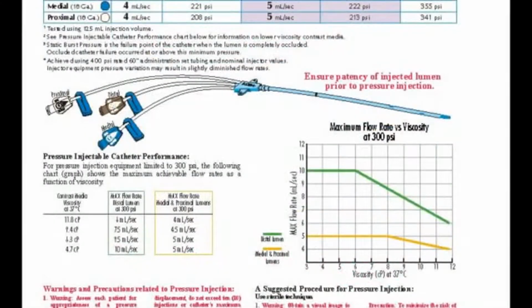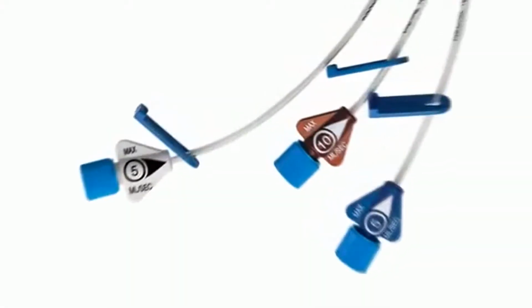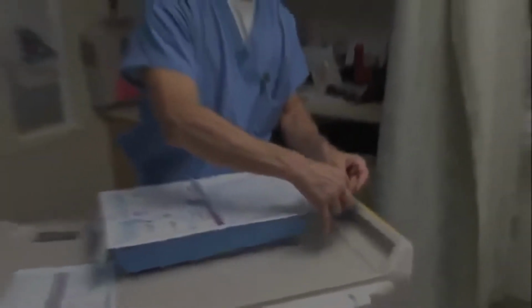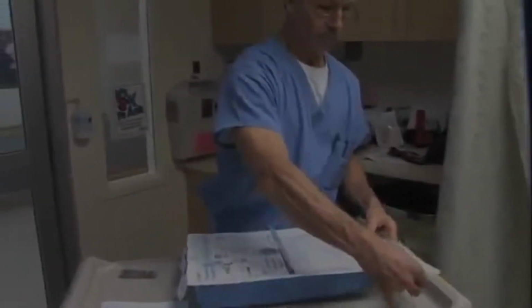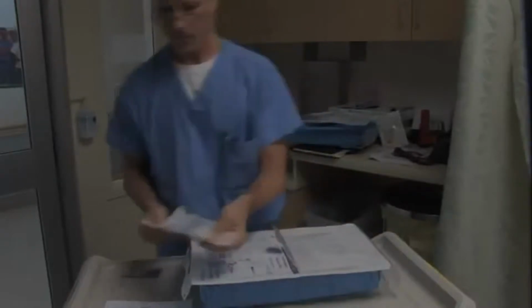If you're inserting a pressure injectable catheter, the system will come with a pressure injection log to use to track CT injections and provide information about the catheter's performance parameters. Add this information to the patient's record for the CT department in the event the patient requires a pressure injection during the dwell of the catheter. The rest of the product-related literature is contained within the pouch for your reference. The ErgoPack contains sterile saline flushes on the outside of the tray. These can be dropped onto the sterile field later in the procedure.